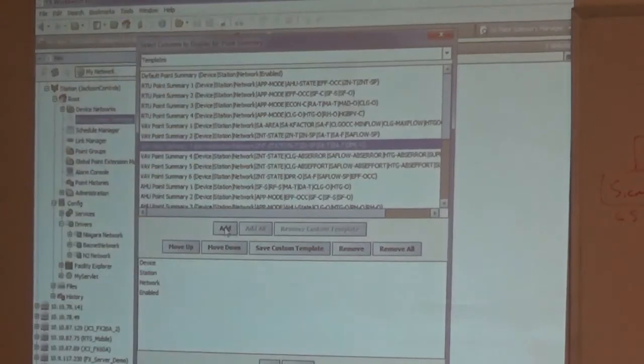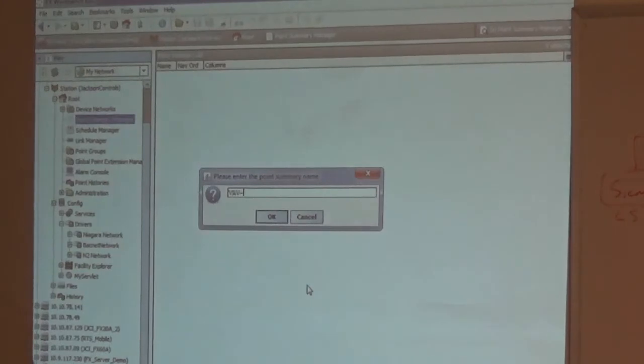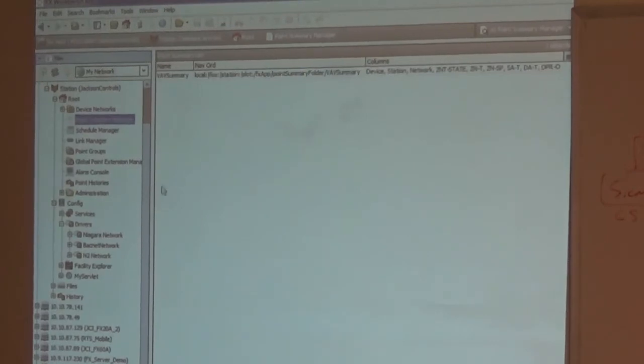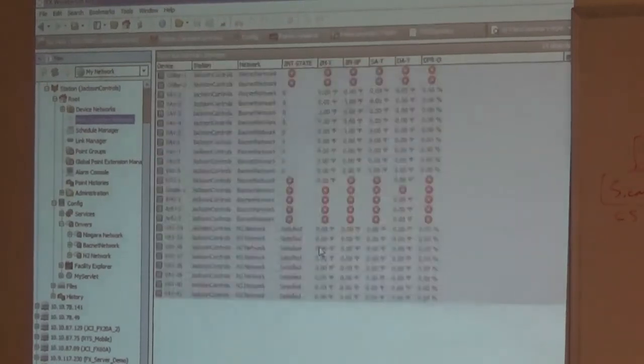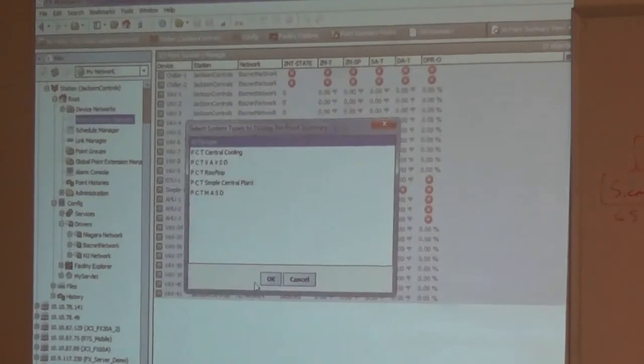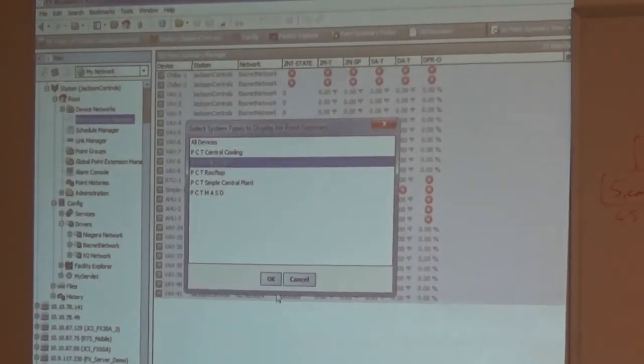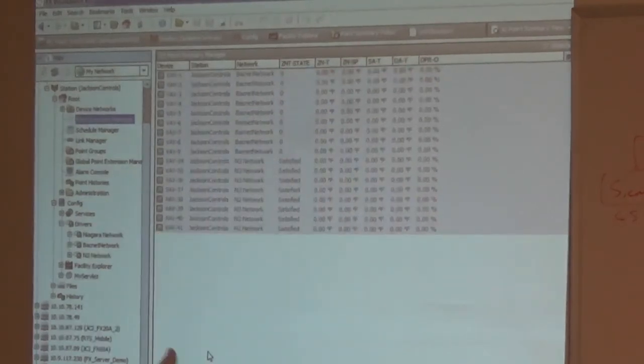So I'll add that on there and hit OK. I'll give it a name, VAV summary, and hit OK. Now it's saved. Every day I can come in here, click twice on this, take a look at my device filter and filter out things I don't need. I just want VAV single duct. Okay, now it's showing those values for every one of my VAV boxes.